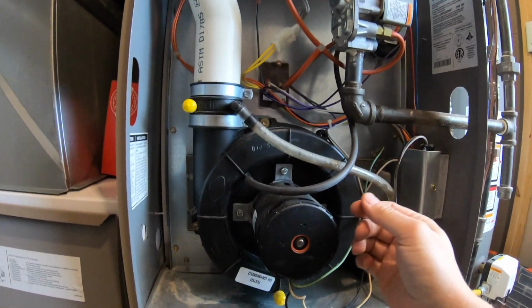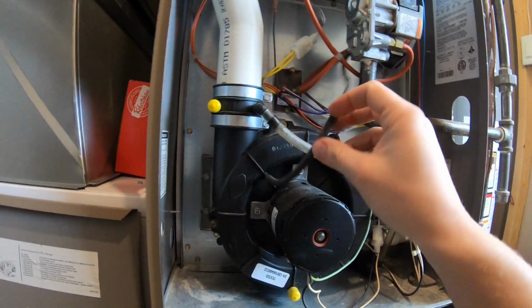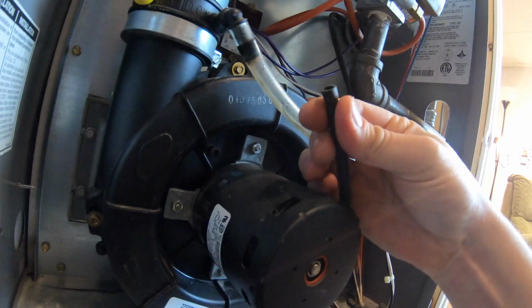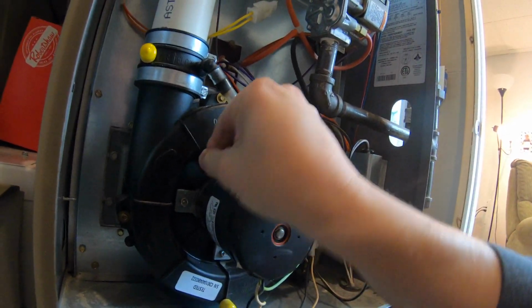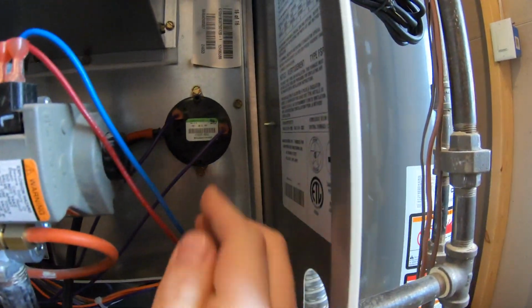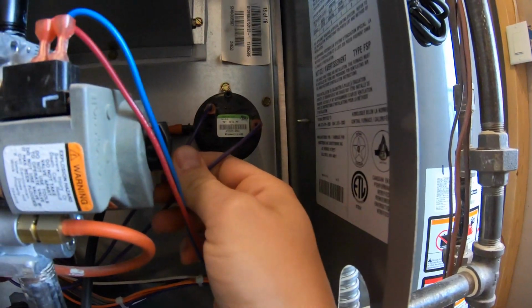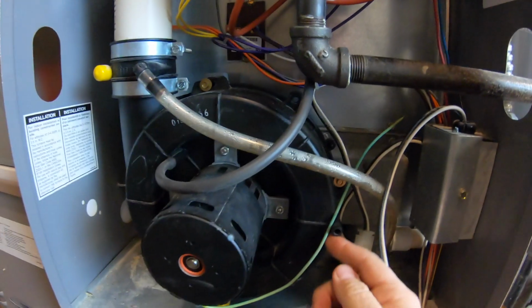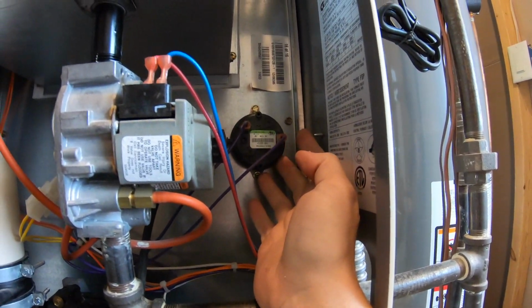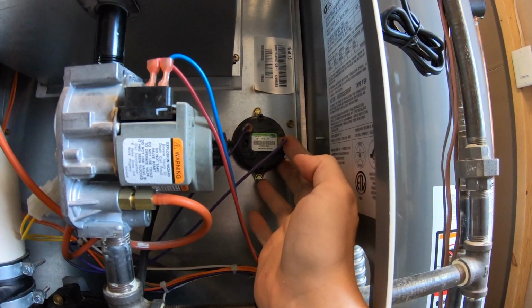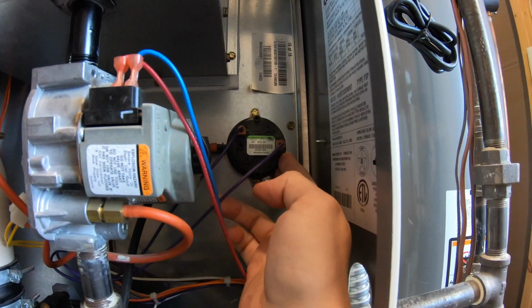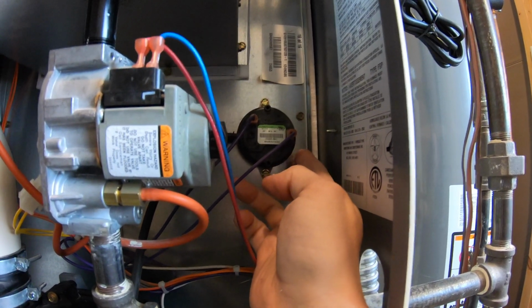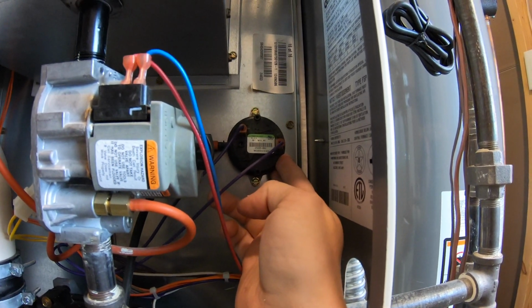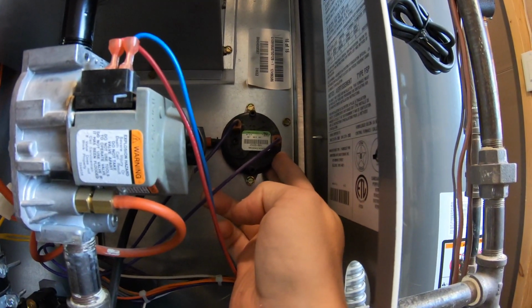So this system has something called a pressure switch on it. This little tube right here is connected to this port. That tube runs up to this switch. This pressure switch is what monitors to make sure that not only is that motor running, but the vent line is clear. This pressure switch, if it is open, will flash a code on your circuit board that says pressure switch stuck open or something to that effect. So if for some reason this isn't closing, that can stop your sequence of operations.